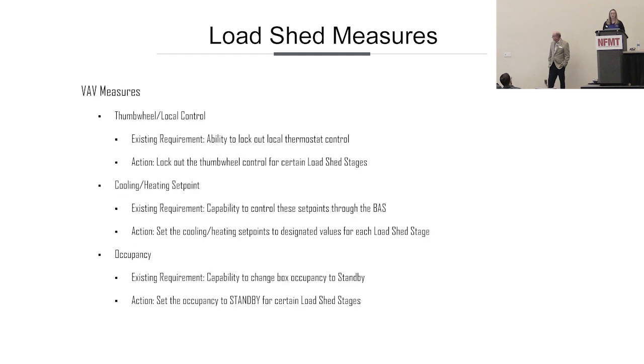So onto the VAVs, their BAS allowed for the thumb wheel control to be locked out or enabled, and so we locked it out so that the occupants couldn't bump it down to 67 degrees, and we kind of had it at maybe 69 to 74 for stage 1, and I don't remember the exact numbers that were on that previous slide, but instead of allowing for them to ramp it up or ramp it down, we kind of had it a little bit more set during those load shed times. And we spread out the cooling and heating set points and used the aux sensors that were installed in the building to show if it was unoccupied. Let's put it in standby mode and close it down.